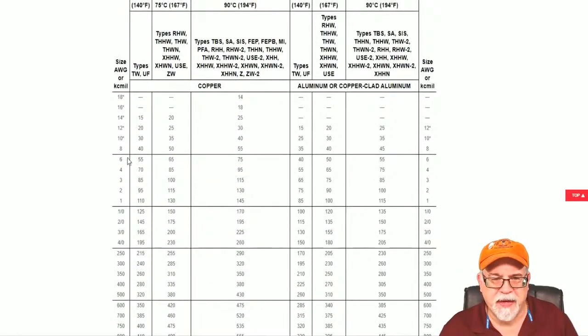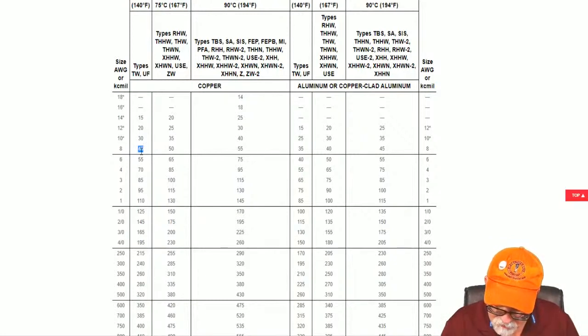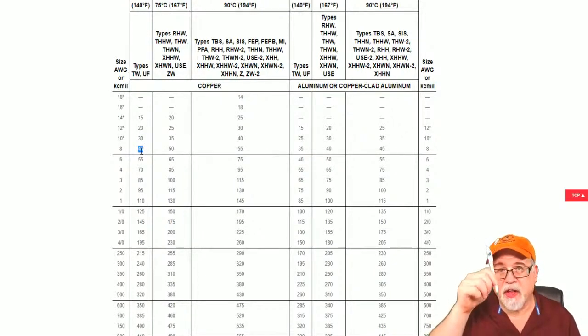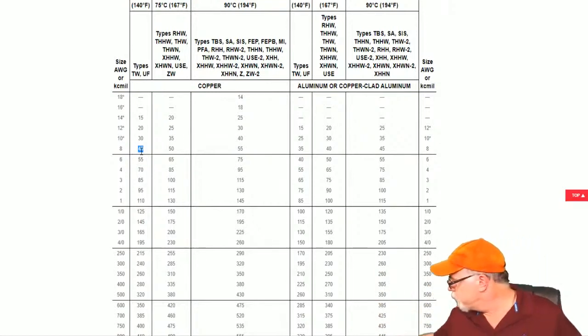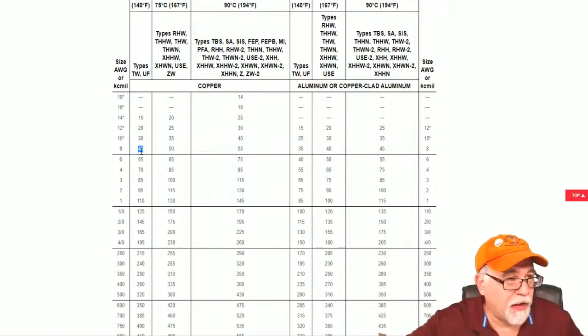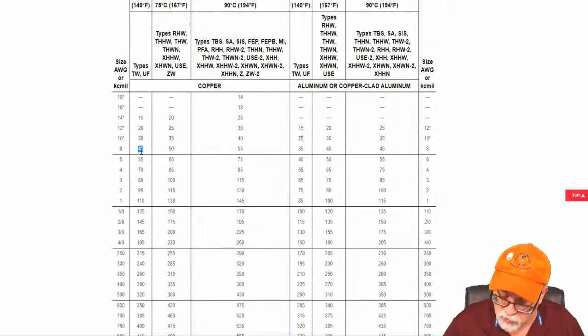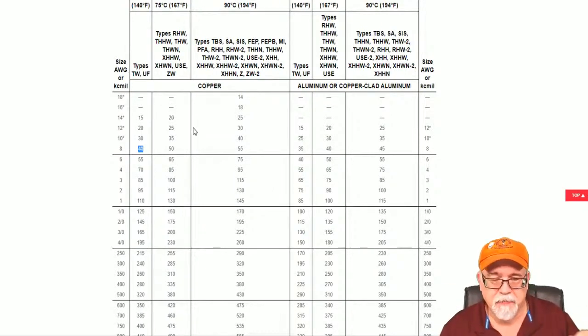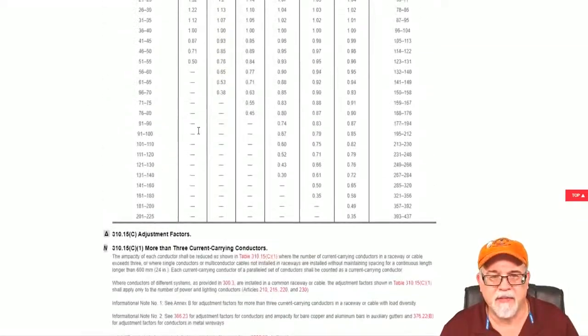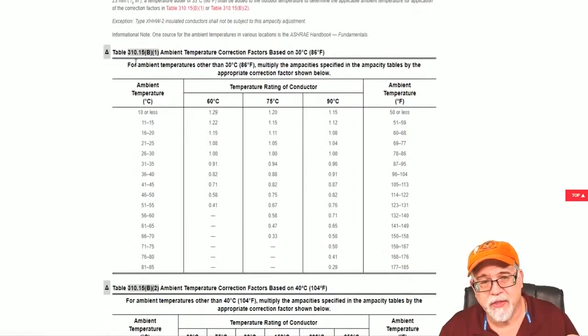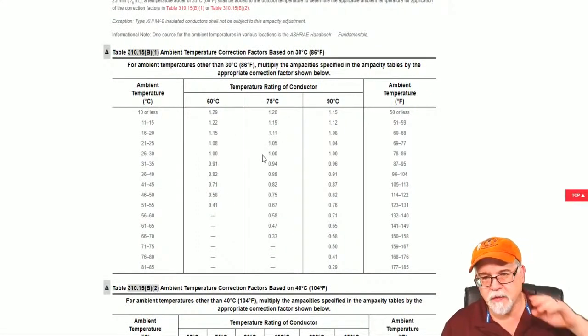So we just wanted to see what is the ampacity of an 8. So under the 60 degree, which is what NMB is rated for, it's 40 amperes. And I want y'all to witness this. Here's another pin that's not working. I'm gonna let y'all know I've got thousands of pins, but the more they don't work, the more they go in the trash. All right, so this is 40 amps. So that's under the 60 degree, okay? Now, one thing that we did remember is that we're also gonna go back here, and this is actually 310.15(B)(1) for the 2020 NEC. Now, this is interesting.